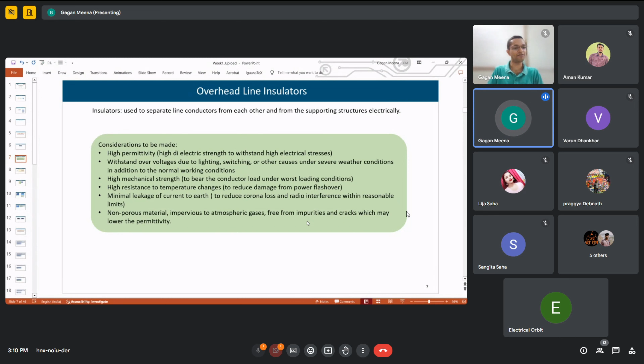And then it should have high resistance to temperature change, so that there is no problem due to flashover. And as I was also telling in the beginning, we don't want any kind of leakage. Leakage of current to the earth via the tower should be very minimal. Then the material should also be non-porous and impervious to atmospheric gases to reduce corrosive effects, that is, degradation of the material. And it should be free from impurities and cracks, because if impurities and cracks are there, then the dielectric strength reduces and flashover increases. All these problems are there.